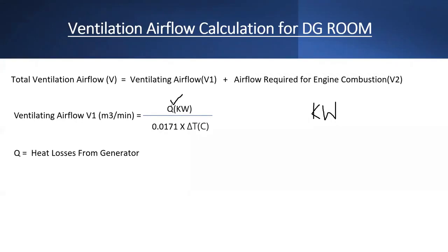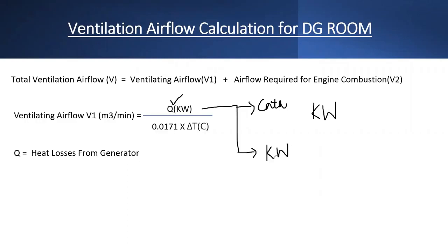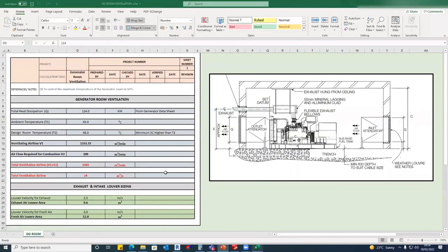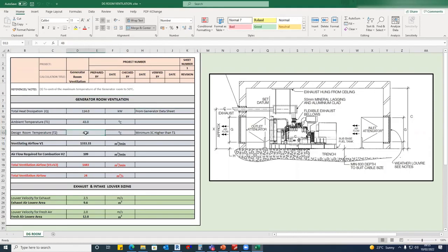There are two ways to get the heat dissipation value. The first case is when we have the generator catalog — we can get all the values from it. The heat dissipation value comes from the generator datasheet. The outside temperature and the design temperature are also inputs — minimum 5 degrees above ambient, and the room temperature should not exceed 50 degrees Celsius.